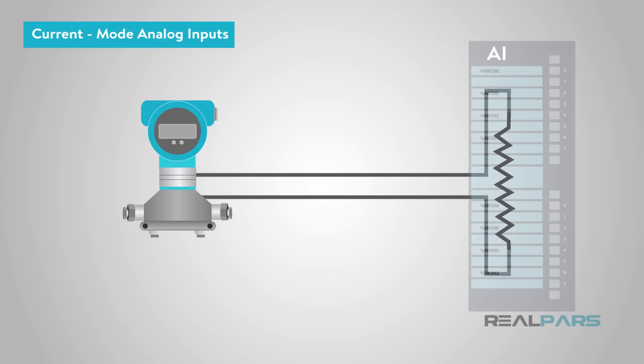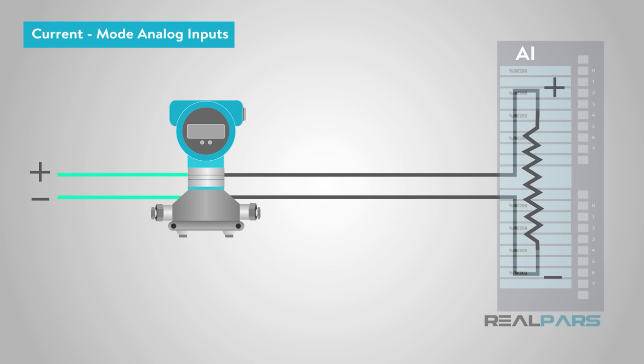This is an example of a device-powered current source. The field device is getting its power from another source. The current signal is sourced from the positive terminal on the measuring device, traveling to the positive terminal of the PLC. Since there is a limit to how much voltage is available in the loop, we will usually limit the overall resistance on the measuring end of the loop to 500 ohms. Often this is called out as part of the field device installation instructions.